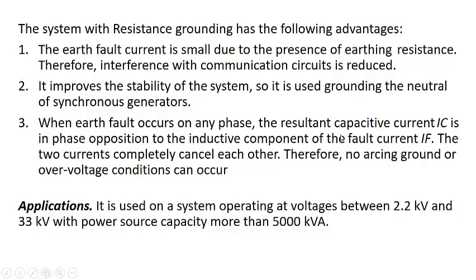When the earth fault occurs on the phase, the resultant capacitive current IC is in phase opposition to the inductive component of the fault current IF. The two currents completely cancel. It is not that they completely cancel each other, but they somehow do. We can say they are in phase opposition to each other, and the arcing grounds are eliminated, which results in a decrease in the over voltages. So this is used in a system with operating voltages between 2.2 kV to 33 kV, and the power capacity is more than 5,000 kVA or 5 MVA. The disadvantage of this case is that in case of the fault, there is a definite power loss in a resistance, that is I square R loss.